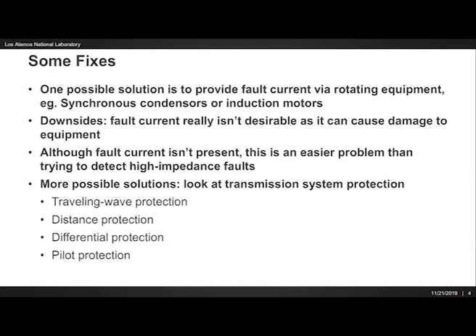That steered me in the direction of transmission system protection, which, although it operates in the presence of fault current, doesn't strictly rely on the ability of generation to provide overcurrent, as is the case of traditional distribution system protection. And there's a number of options which are listed in the slide, of which admittance or distance protection is one of them. In this presentation, I prefer to use admittance protection because, as I'll show further on, in microgrids it's generally fairly difficult to estimate the distance of a fault, especially in ones that are relatively spatially compact.